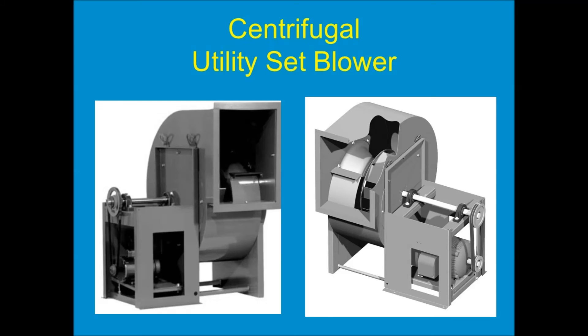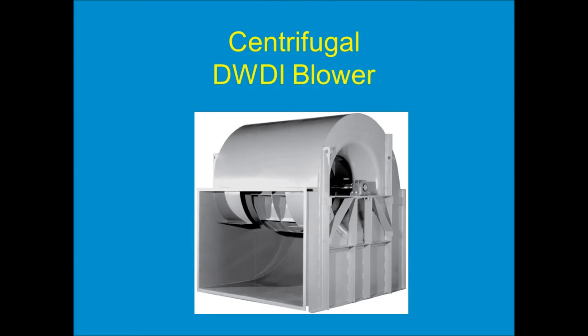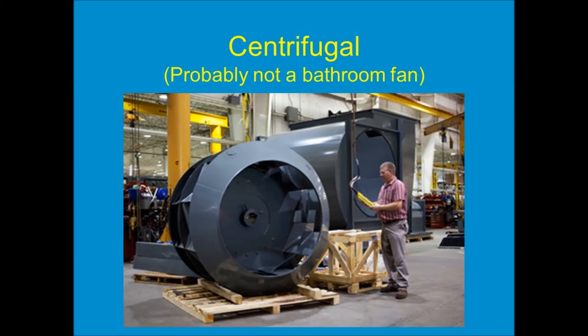The centrifugal impeller is also what's used in a big double width double inlet blower. Some of these fans are the size of a house, but it's the same principle — the blades create a low pressure in the center, air is drawn in from both sides, then it follows the shape of the housing and discharges out the lower left of this fan. This is a 73-inch diameter centrifugal impeller — that's a pretty big fan. I suspect this is not the fan they're using for bathroom exhaust, but you never know.